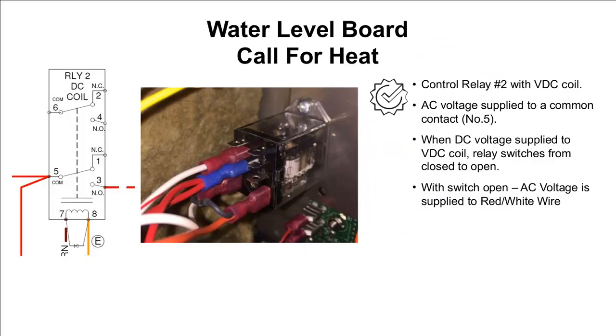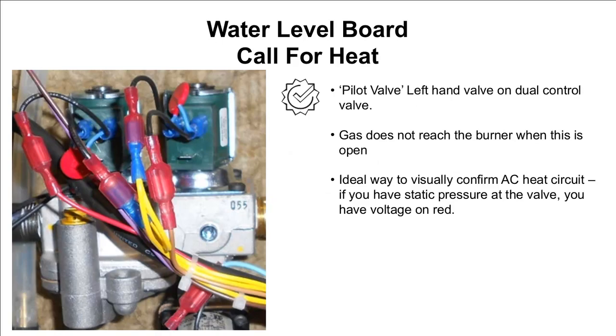So where does that power go once it's hit the red wire? The first stop, as we would call it, is here on contact 5 of control relay 2. And this voltage doesn't go anywhere at this point. It is just sitting and waiting here, and it relies on the DC circuit to allow it to continue.